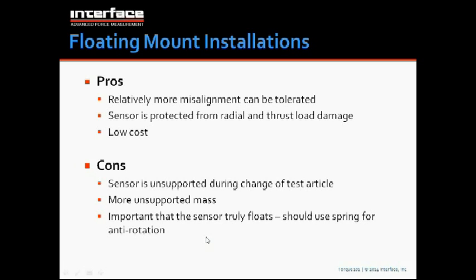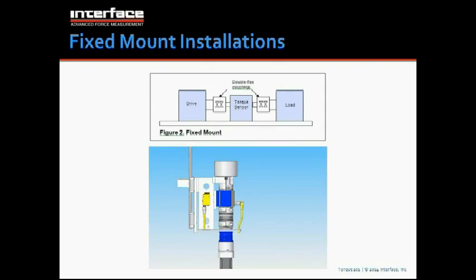And then also, in a floating mount, it's important that the sensor actually floats. A lot of people have a tendency to want to bolt the housing to something to keep it from spinning, and that may be much more tightly connected than it should be. It should truly float with a rubber spring or some kind of flexible mount. As soon as you try to bolt the housing to something, it pulls the housing towards that item and starts to put a radial load into the bearings, which is undesirable.